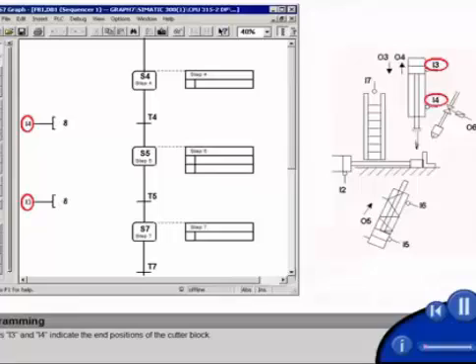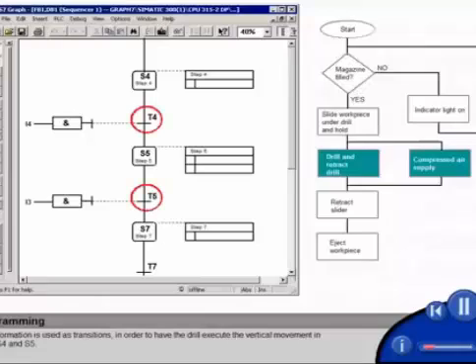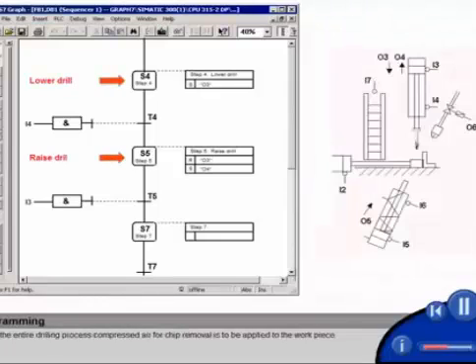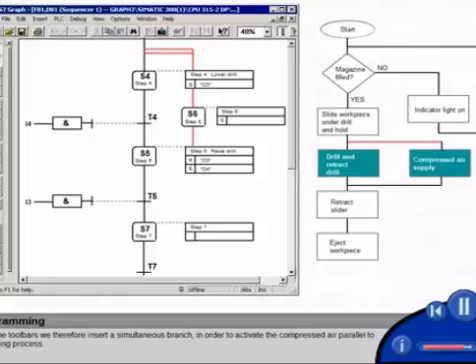Sensors I3 and I4 indicate the end positions of the cutter block. This information is used as transitions, in order to have the drill execute the vertical movement in steps S4 and S5. During the entire drilling process, compressed air for chip removal is to be applied to the workpiece. From the toolbars, we therefore insert a simultaneous branch, in order to activate the compressed air parallel to the drilling process.